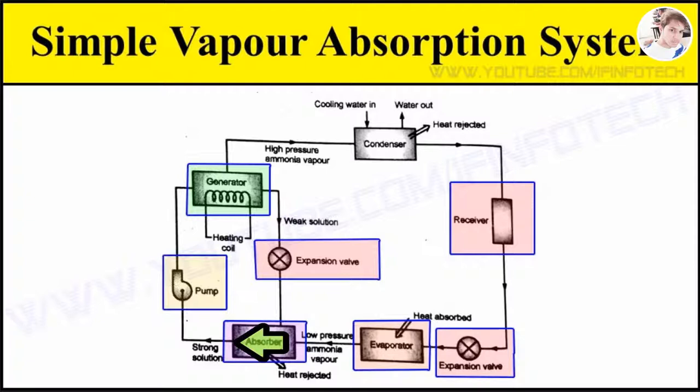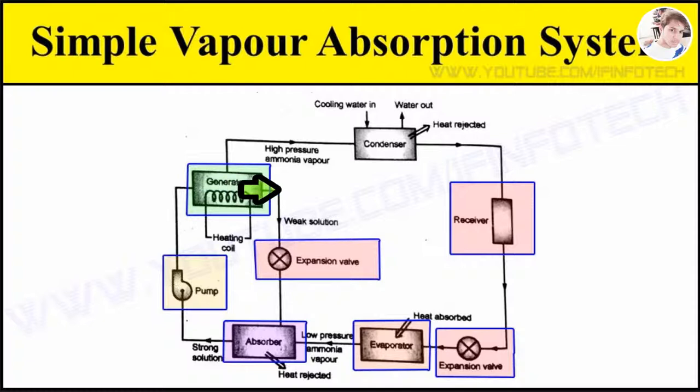The strong solution formed in the absorber is pumped to the generator by the liquid pump, which increases the pressure of the solution. The strong solution of aqua-ammonia in the generator is heated by some external source. During the heating process, ammonia vapor rises at high temperature and high pressure, leaving behind the hot weak aqua-ammonia solution in the generator.